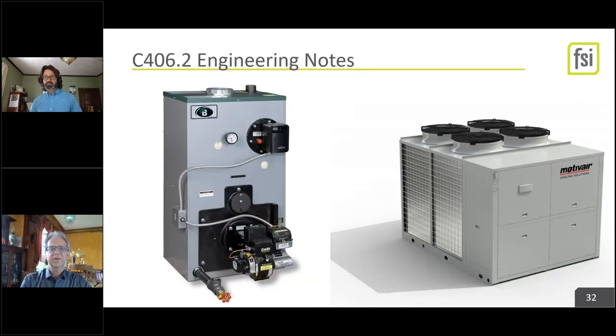Adding engineering notes. What does it take to get better than 15% better than code for the number two option? You get to average by capacity, so you do a capacity-weighted average, and it has to be an average better than 15%. Everything has to be 5% better or more. Most equipment types can achieve this, but chillers and oil-fired boilers might not get there. Some chillers might just be limited.